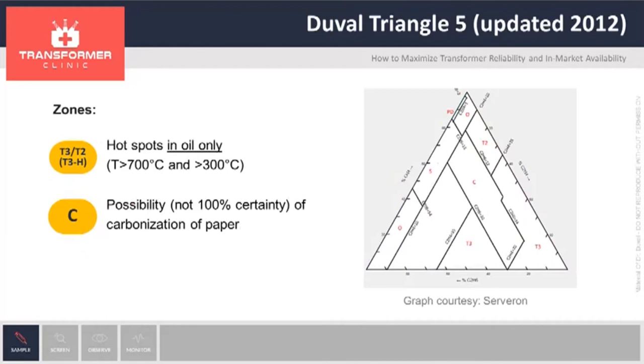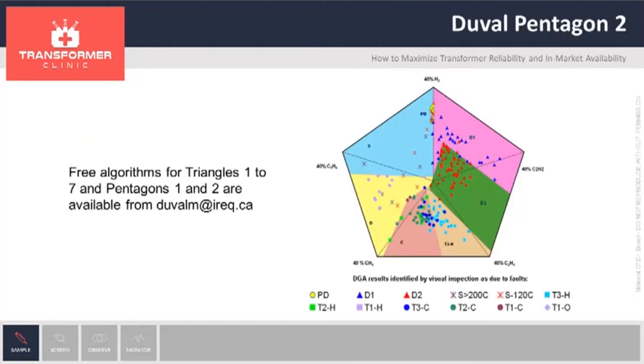Triangle 5 allows distinguishing between high temperature faults in oil only, of lesser concern, and those with possible carbonization of paper C, potentially more dangerous. Triangle 5 uses methane, ethylene, and ethane — the so-called high temperature gases, or hot metal gases. Pentagon 2 allows identification of the three basic electrical faults PD, D1, D2, and the three subtypes of thermal faults S, O, T3 in oil or T3H, and C. Pentagon 2 uses the same five gases as Pentagon 1.